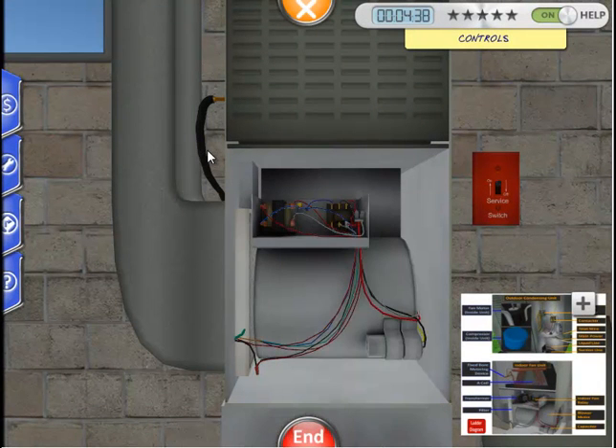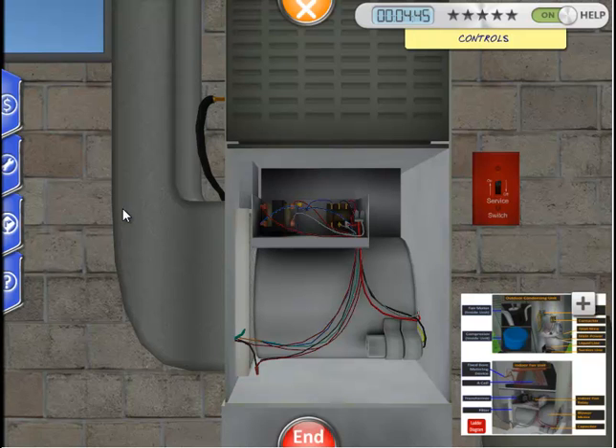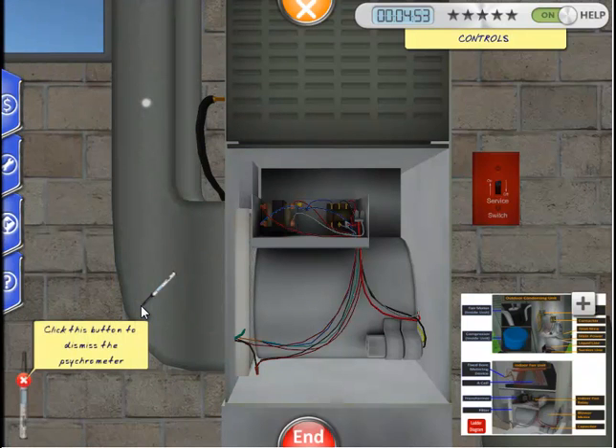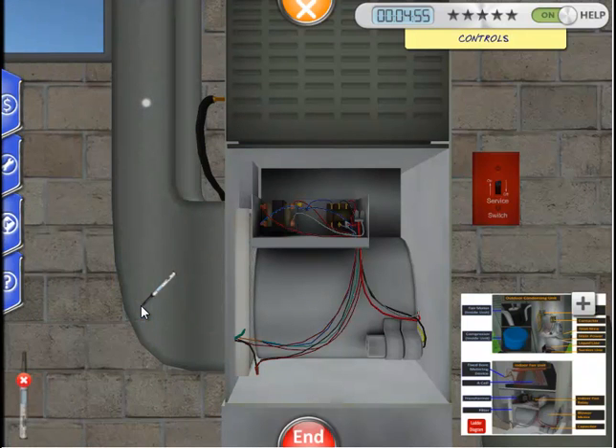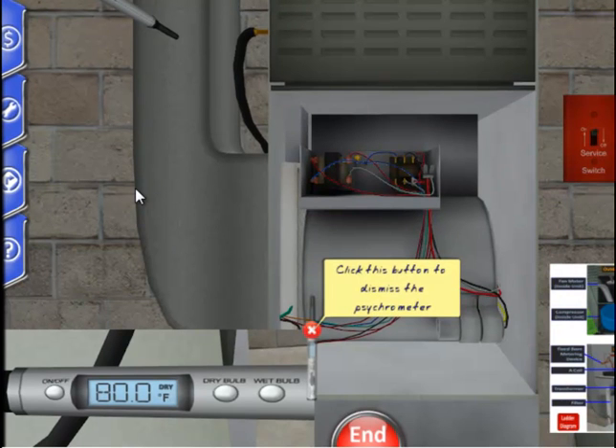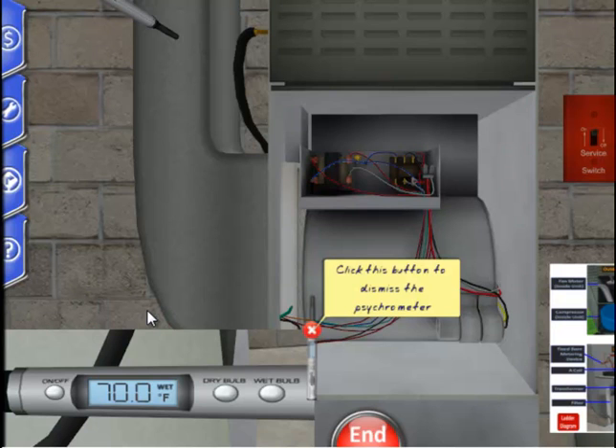Now we're going to check the superheat. First, we will want to measure the indoor wet bulb temperature. We will do this with the psychrometer at the return vent of the indoor unit. Let's open up our tool tab and select the psychrometer. We will place the icon in the glowing hot spot in the return vent. Now let's click the wet bulb button because we want to measure wet bulb, not dry bulb temperature. We have a wet bulb temperature of 70 degrees Fahrenheit.